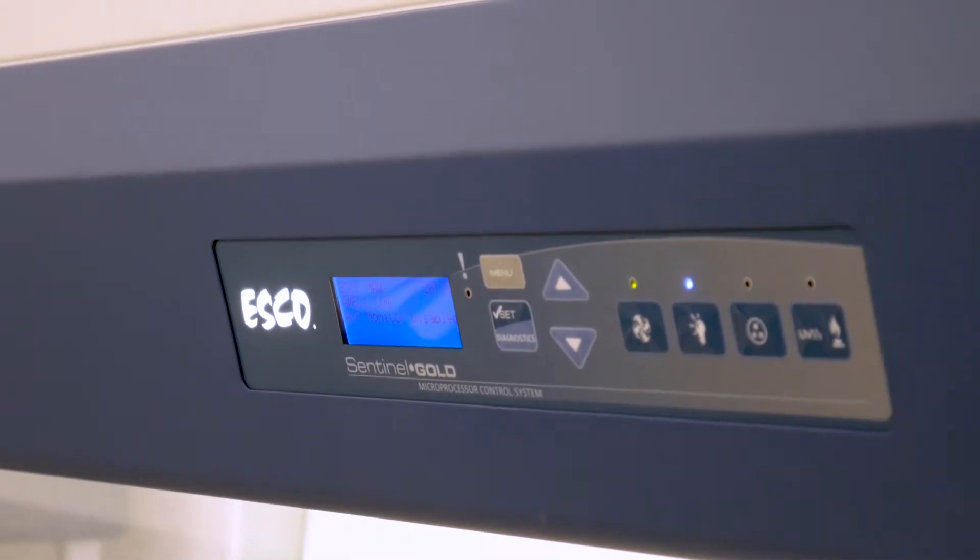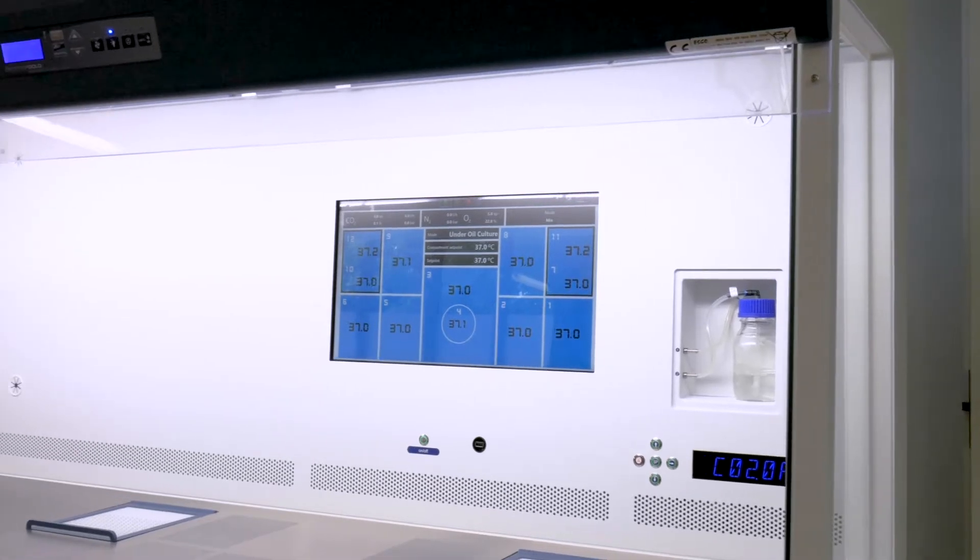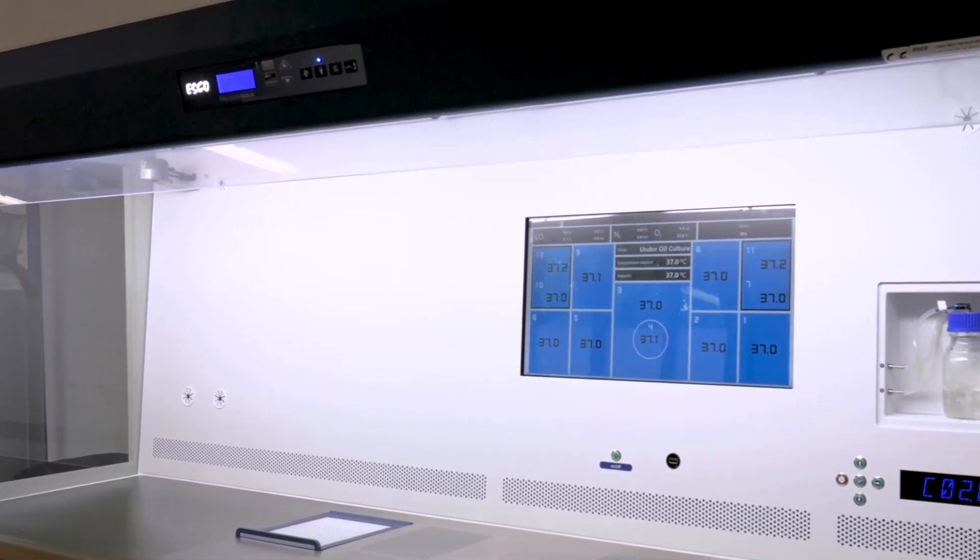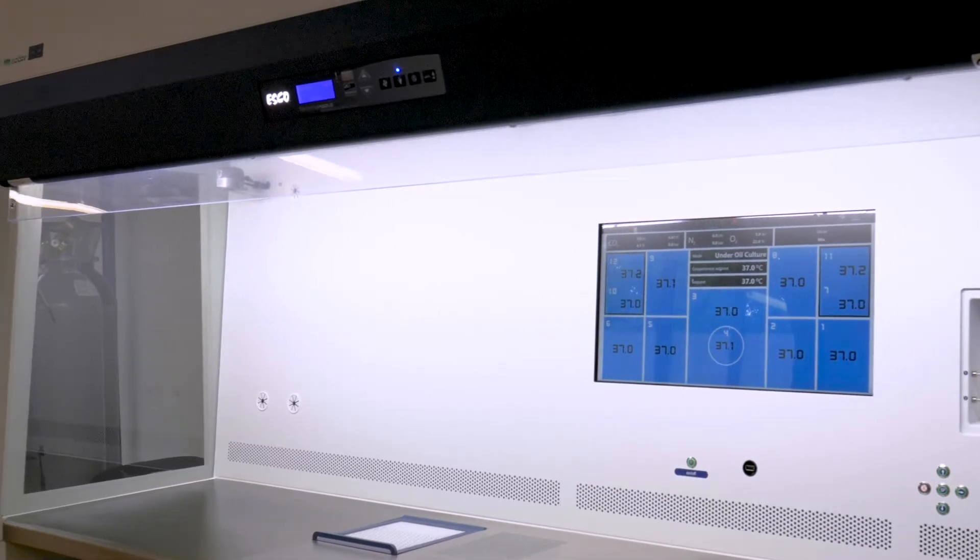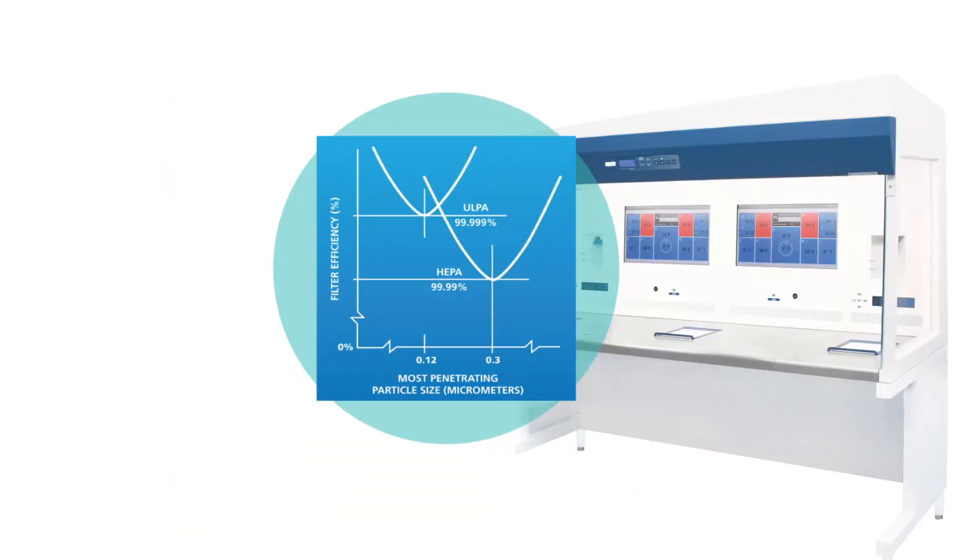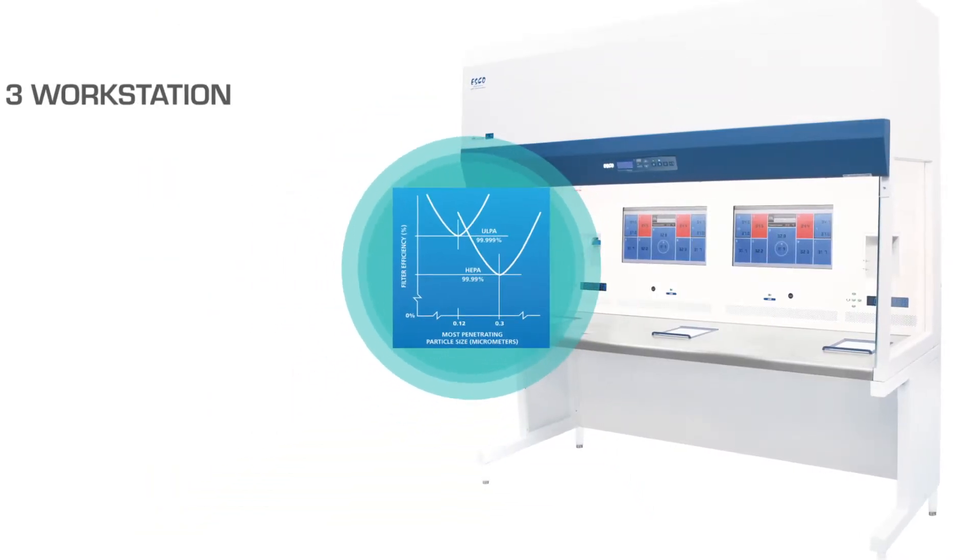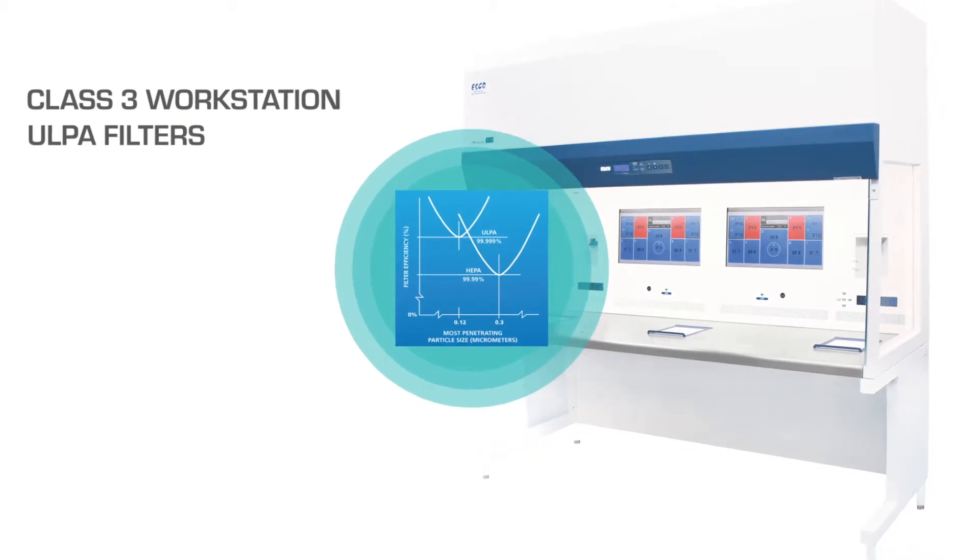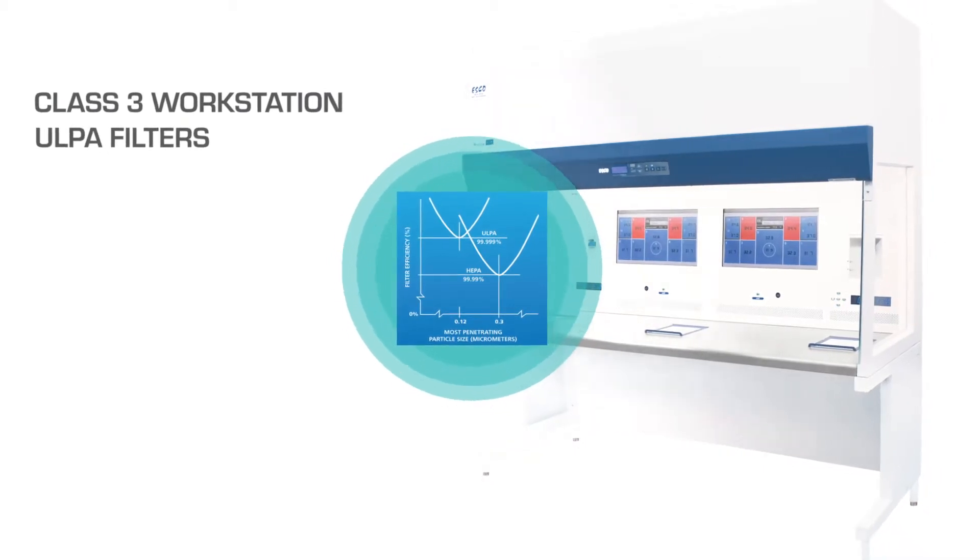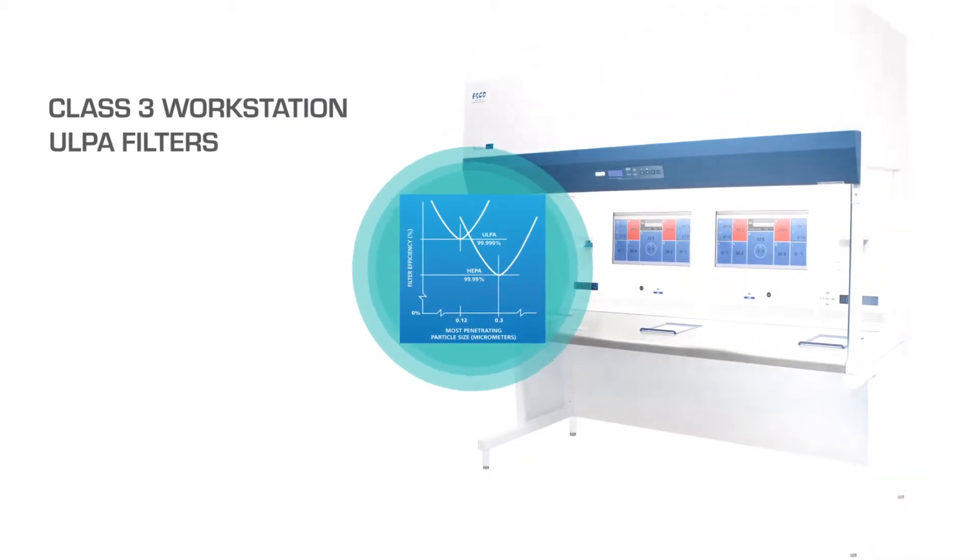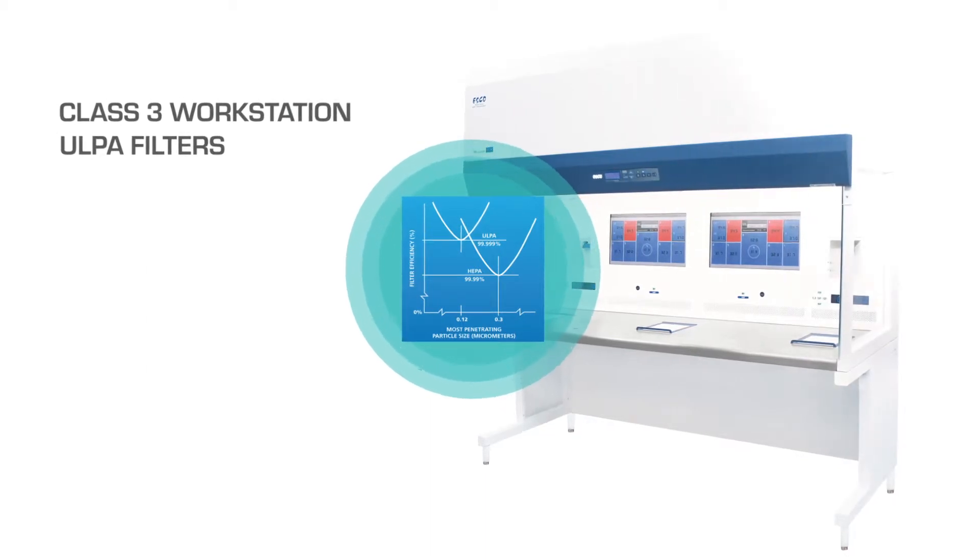It's a vertical laminar hood having a multizone heating system that have its own heating elements and sensor for uniform heat distribution. ESCO Multizone ART Workstation provides ISO Class III air cleanliness with the work zone as per ISO 14644.1.